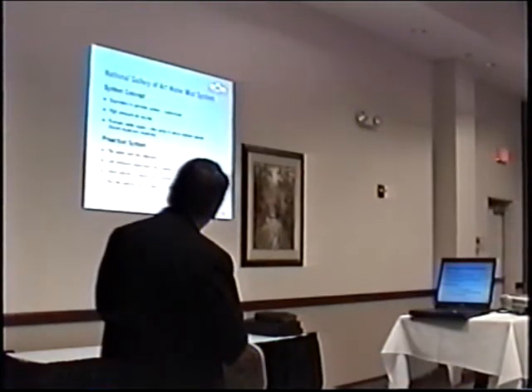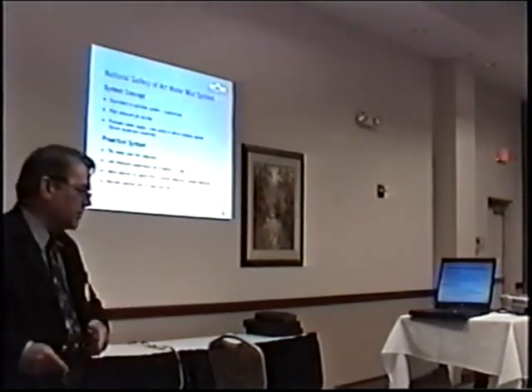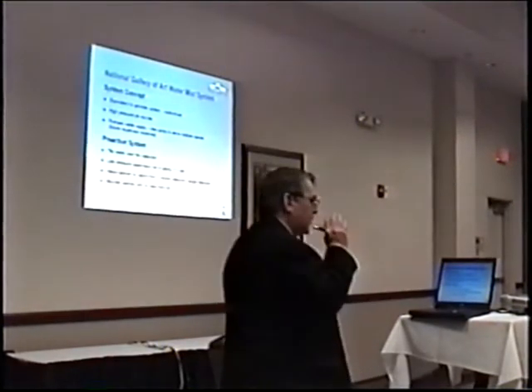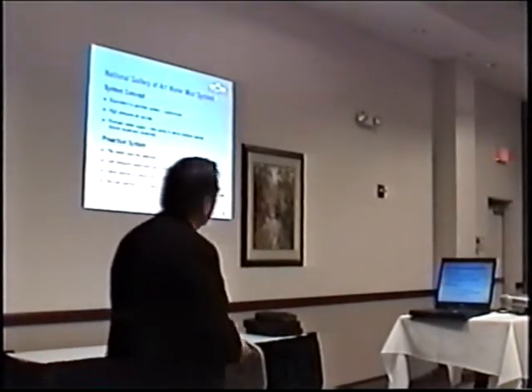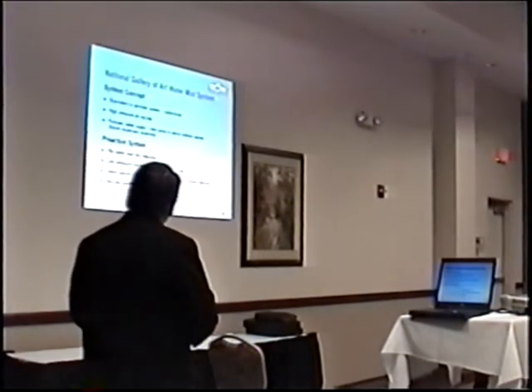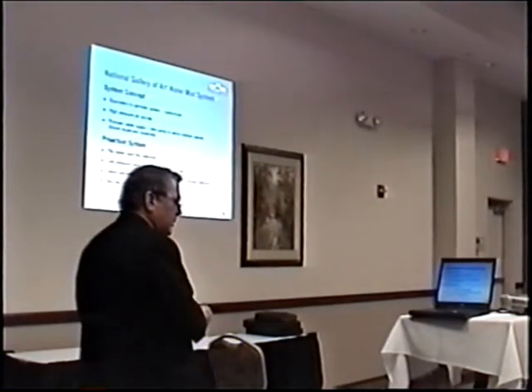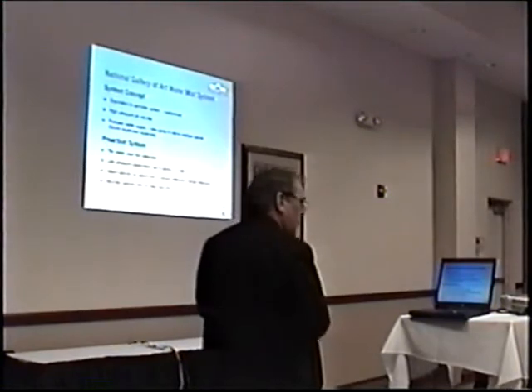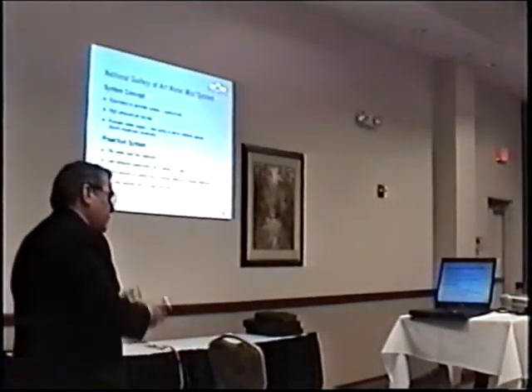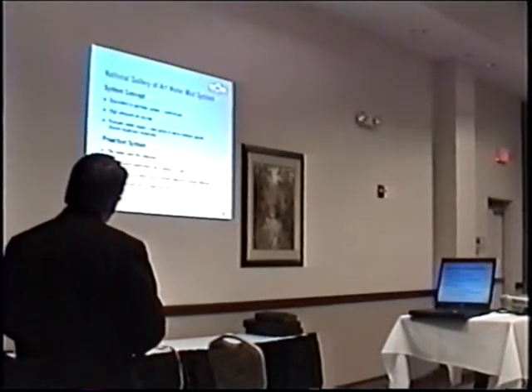Pre-action systems. Previously I was fairly reluctant to get into pre-action systems, but now I sleep better every night of the week because this is a pre-action system. All my concerns about water hammer and all the other things I might be concerned about, I'm quite comfortable with the fact that these systems are... I'm not going to have a nozzle failure. Those are 2.5 millimeter glass bulbs in those nozzles. I know there have been a lot of failures of 3 millimeter glass bulbs in standard sprinklers. And again, the fact this is a pre-action system makes me feel a little bit more comfortable about that.